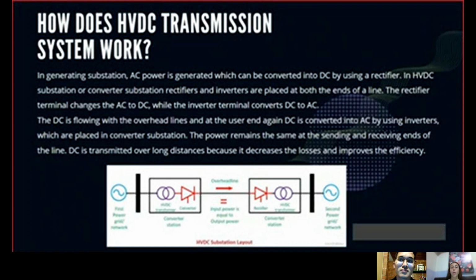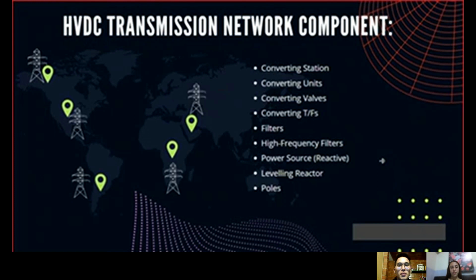DC is transmitted over long distances because it decreases the losses and improves the efficiency. A system having two converter stations and one transmission line is called a two-terminal DC system or a point-to-point system. Similarly, if a substation has more than two converter stations and interconnecting DC lines, it is called a multi-terminal DC system. Okay.